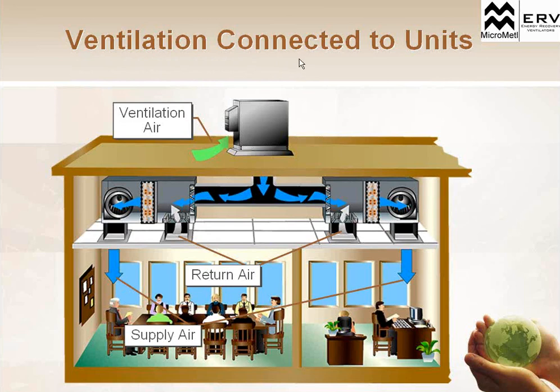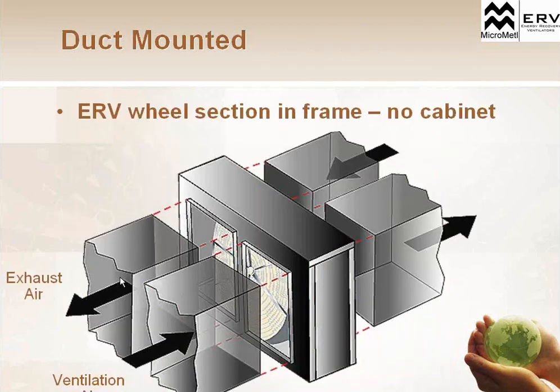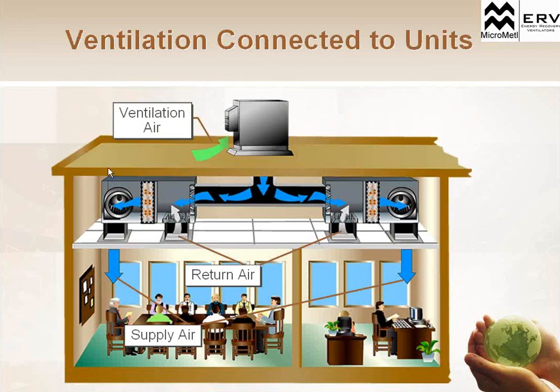Conversely, we can connect that ventilation system to the HVAC unit. So we have just the ERV unit on the space, recovering the exhaust air and bringing that ventilation air directly into the HVAC system, whether it be a rooftop unit, a fan coil or an air handler. We would bring that in, mix it with return air, and then size the HVAC system to completely temper that air from that 81 degrees down to the 75 for supply into the space.